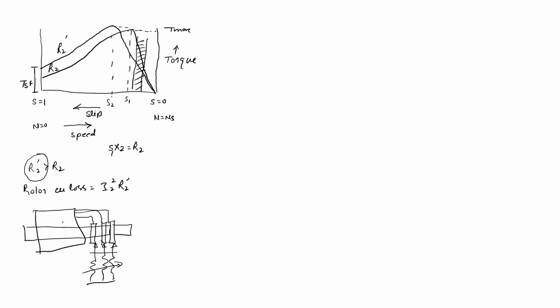In many applications we do not want any type of sparking, otherwise it will catch fire, like in petrochemical industries, or industries where ethane and methane gases are present. So as a flame proof motor, or where there should be zero sparking in the plant itself, the slip ring motor is not advisable to use in such industries. So the only option which remains is the squirrel cage motor.